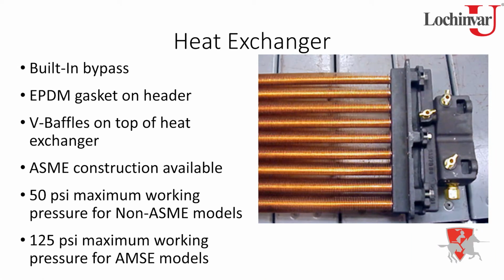Now, there are options for bronze. So if you do want to go bronze, maybe you've got a saltwater pool application, a bronze header is available, as well as what's called copper nickel tubes. The example that you see here is a standard copper heat exchanger. You can tell that by the nice shiny bright copper. So that's pure copper.